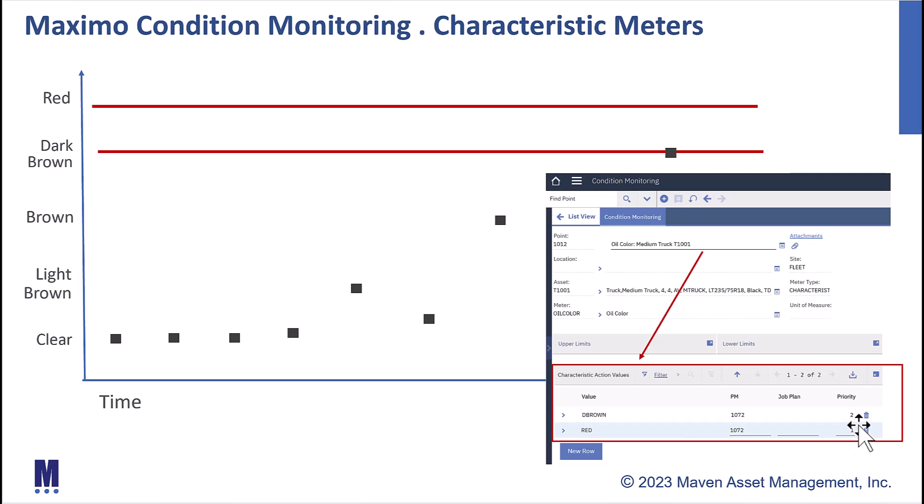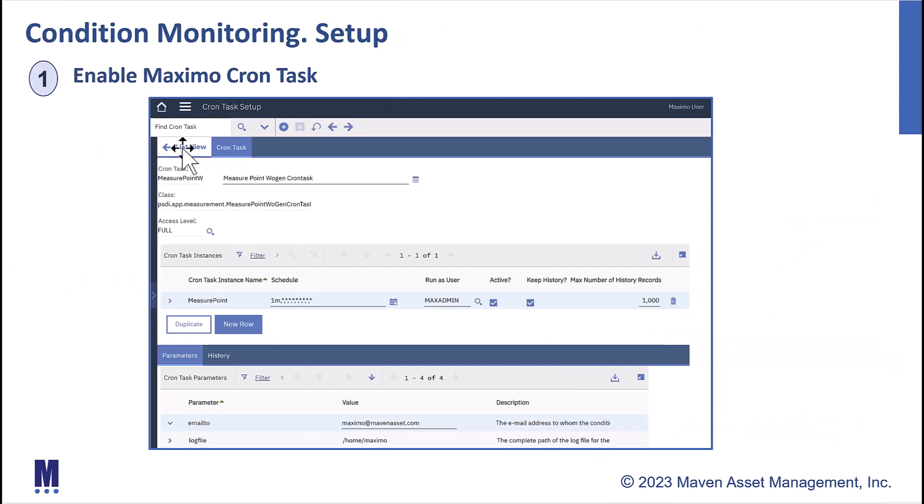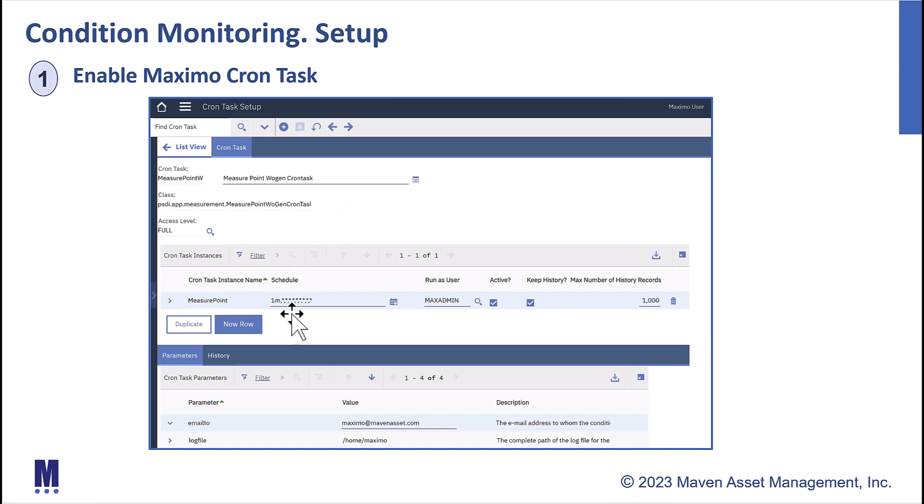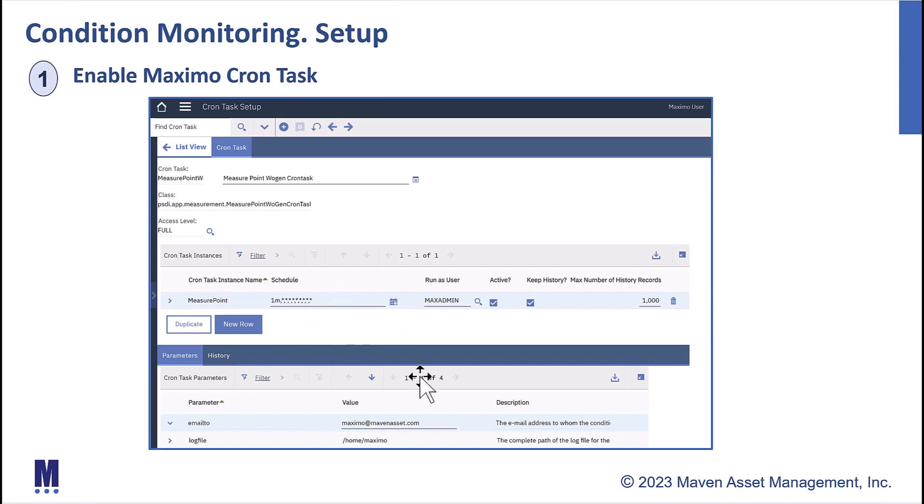Now to enable condition monitoring, there's just a few quick things that you have to do. First off, there's a Maximo cron task. It's the Measure Point WoGen cron task. It is not enabled by default, so you have to activate it, and you have to add that cron task instance. I want to highlight that I do have a minute here, as shown in our demonstration today, that we'll use. This is not a realistic value for a production environment. I'm just using that for our demo that we'll have in just a few minutes.